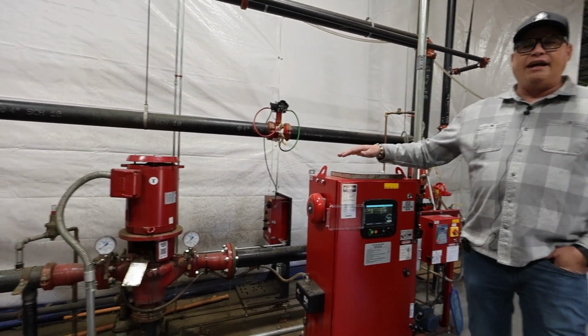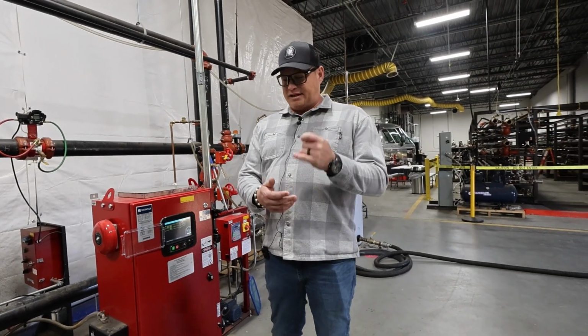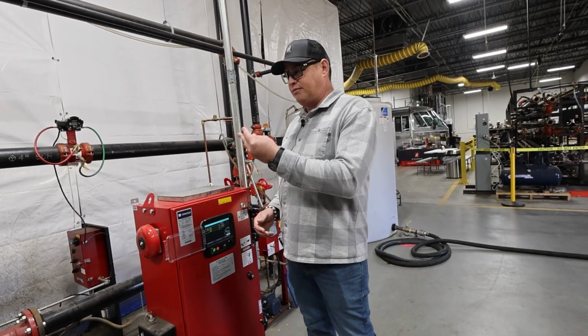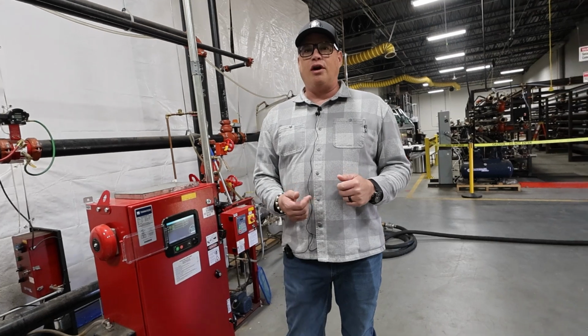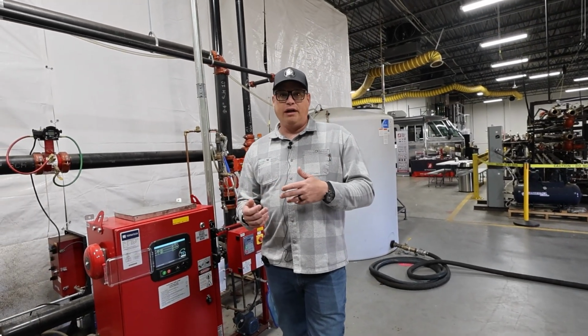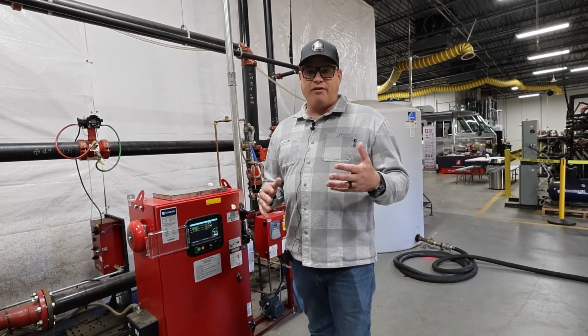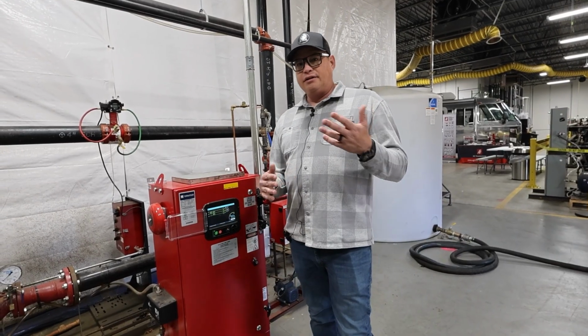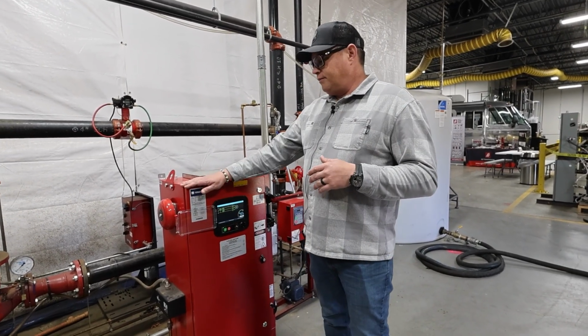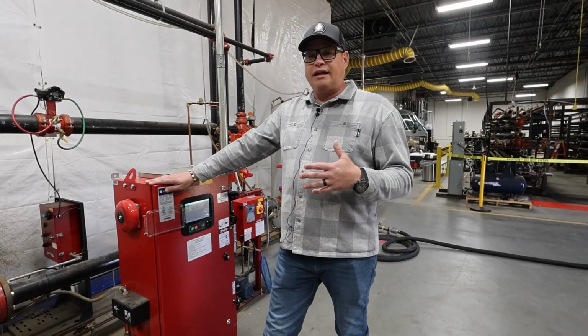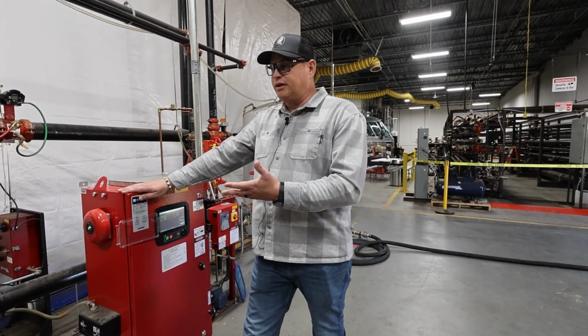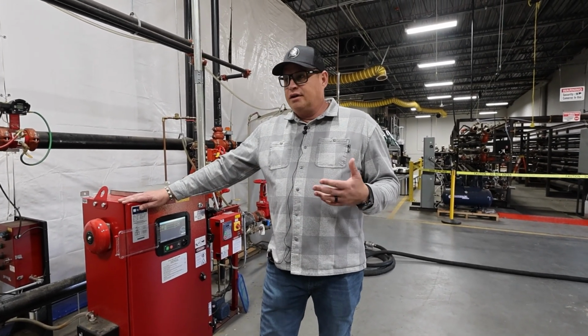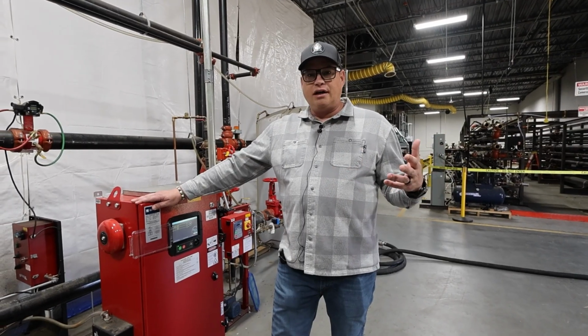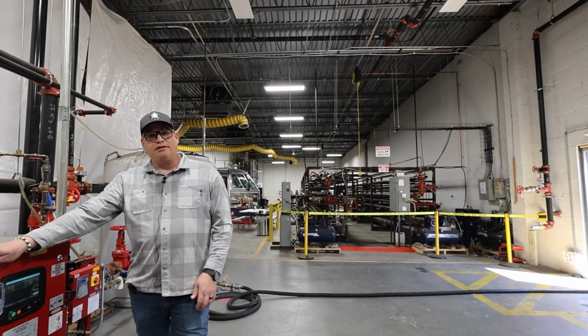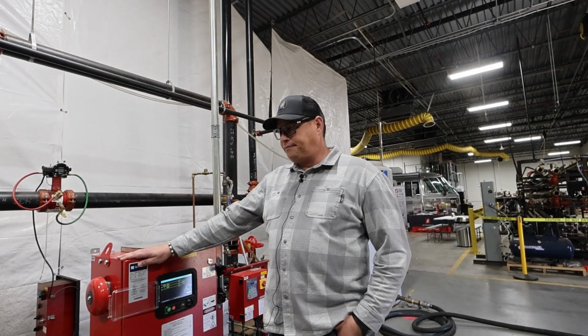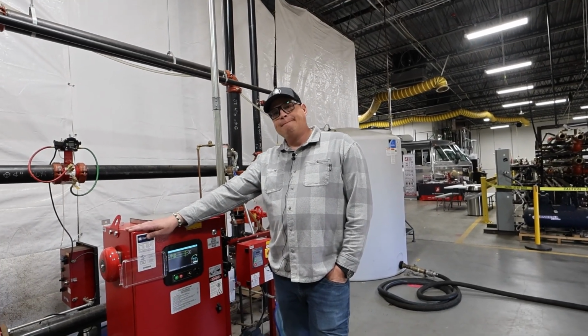Having done all that, I'm going to take recordings of all of these readings, my speed, my temperature, my suction, my discharge, and I'm going to put them into a log. Yep. It'll be a manual log that we would probably put into a different type of software depending on the company you work for and the service software that you use. We're going to do this every single month and keep these good records. Depending on your building, if you're insured by FM or one of these big insurance agencies, they want all these records. And they want to maintain them on site for usually, I've had some that say a minimum of 7 years.